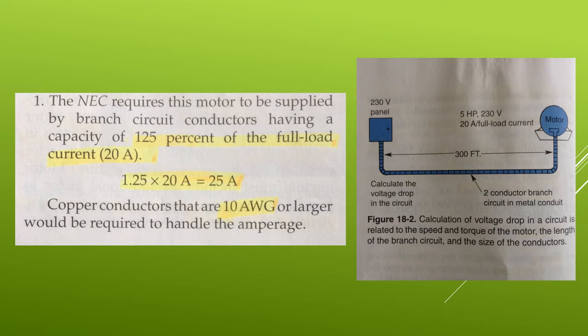As specified by NEMA, motors are designed to handle a 10% fluctuation in voltage above and below the rating on the nameplate. You may not be able to control the typical voltage changes that occur as loads are placed on and off the electrical system, but you can control the amount of voltage drop by installing the proper conductors. Refer to figure 18-2 as you determine the proper conductors to install. In this example shown on the screen, step 1, the NEC requires this motor to be supplied by branch circuit conductors having a capacity of 125% of the full load current, or 20 amps. So we multiply 1.25 times 20, which is 25 amps. So copper conductors that are 10 AWG or larger would be required to handle the amperage.